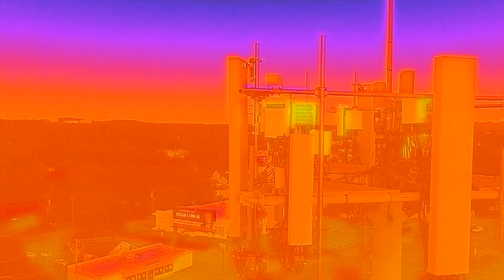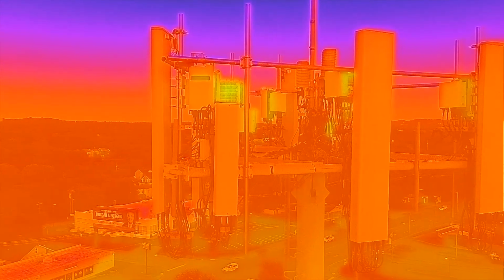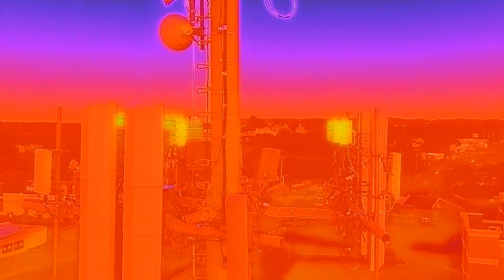Pull back out of here a little bit. A little too hazardous up in that. Get a real nice overall scan all the way down this. Ambient's 85 degrees. Right there, 115 degrees, right in the center of that box. Hope that's the right operating temperature.